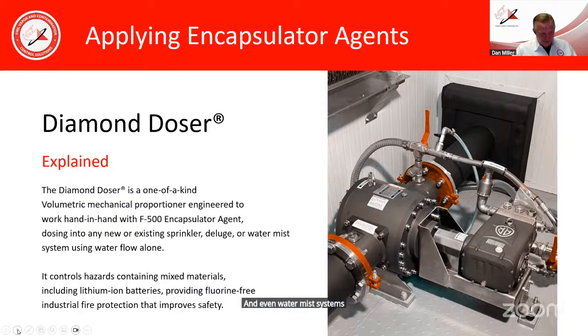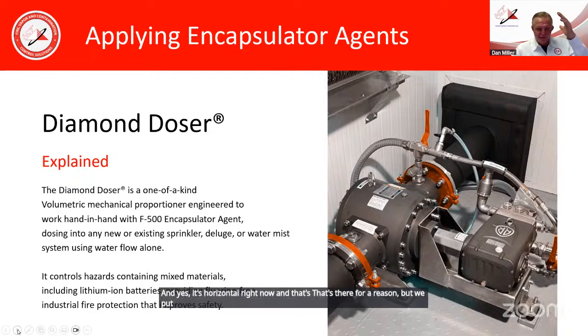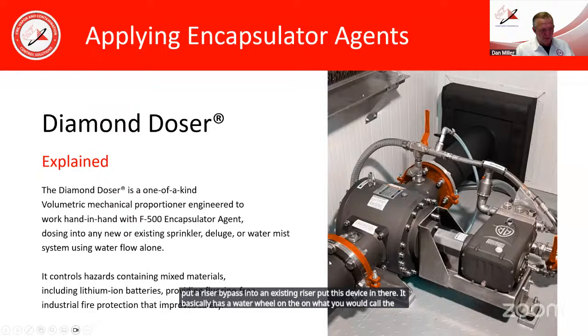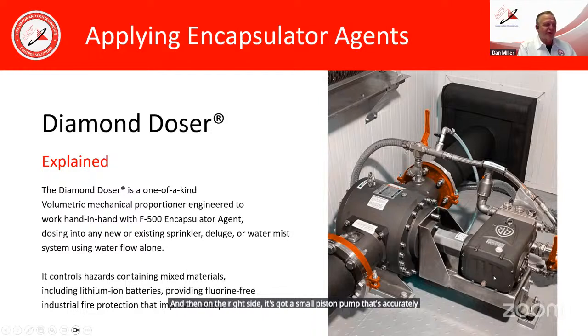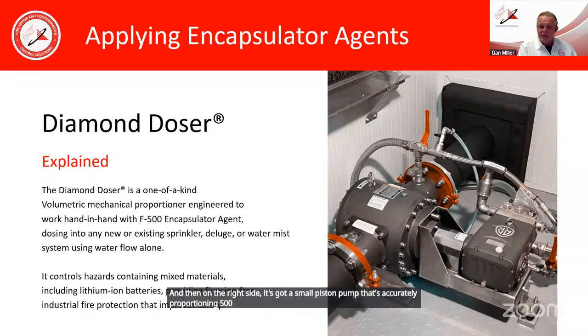This device basically goes in the riser. It's horizontal right now for a reason - we put a riser bypass into an existing riser and install this device there. It has a water wheel on what you'd call the left side of the waterway, and on the right side, a small piston pump that accurately proportions F500 into that riser.